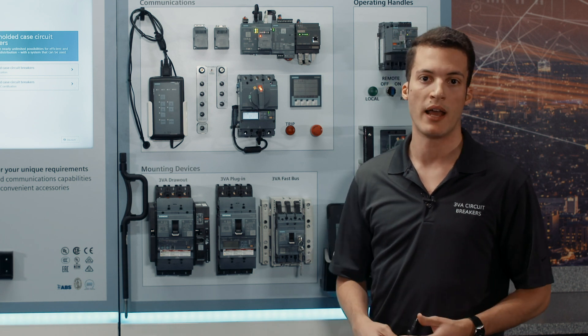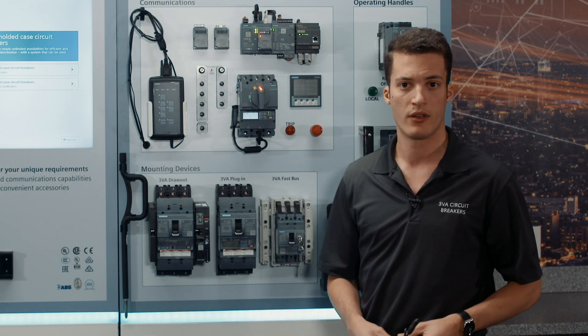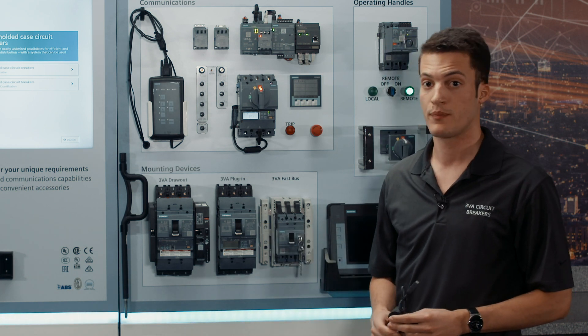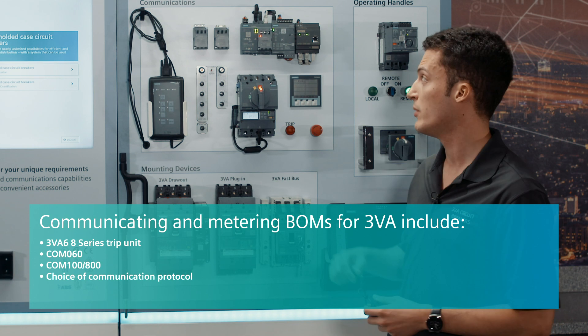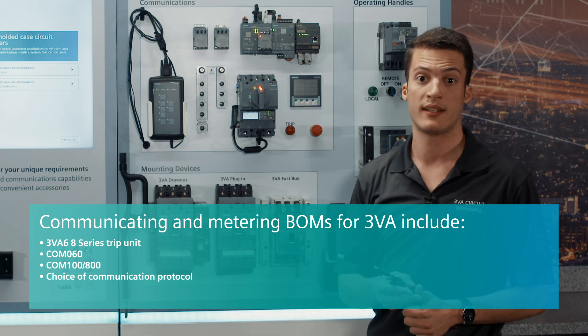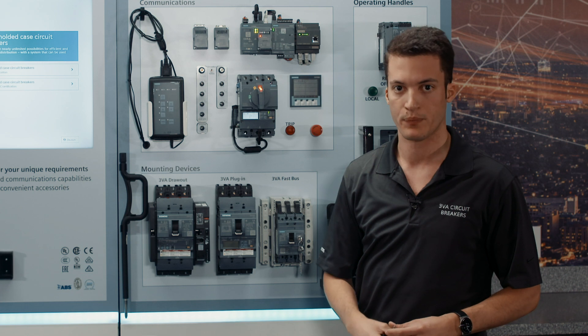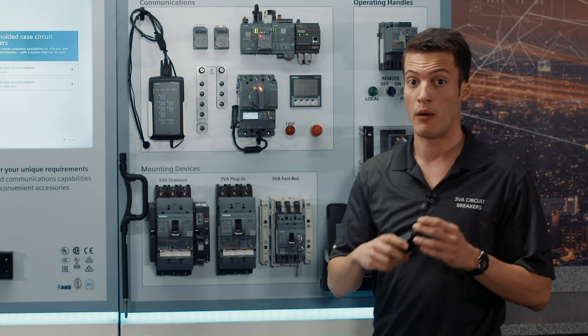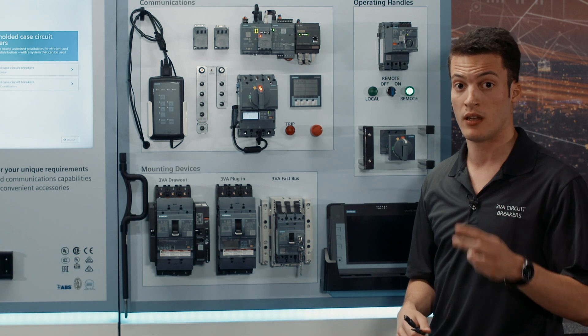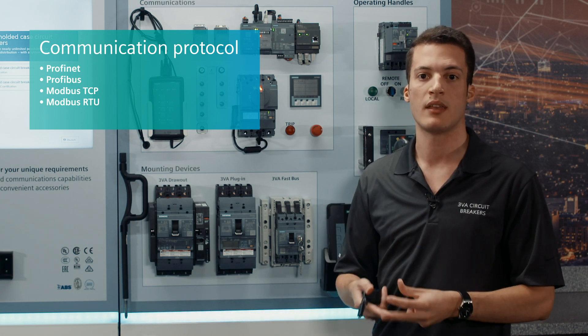The way communication and energy measuring work for 3VA6 is fairly simple. You no longer need to buy external current transformers and an energy meter — you have everything already included inside the breaker. You need to get one of these accessories called COM060, and this accessory goes on the right pocket of the 3VA6. Then this end is connected to what we call our data server — COM800 or COM100 — and you're done. COM100 is a data server connected to up to one circuit breaker, and COM800 is a data server connected to up to eight circuit breakers at the same time. You can achieve all this with our 3VA6 using an ETU Series 8, and you can also use very different types of communication protocols — namely PROFINET, PROFIBUS, Modbus TCP/IP, and Modbus RTU.